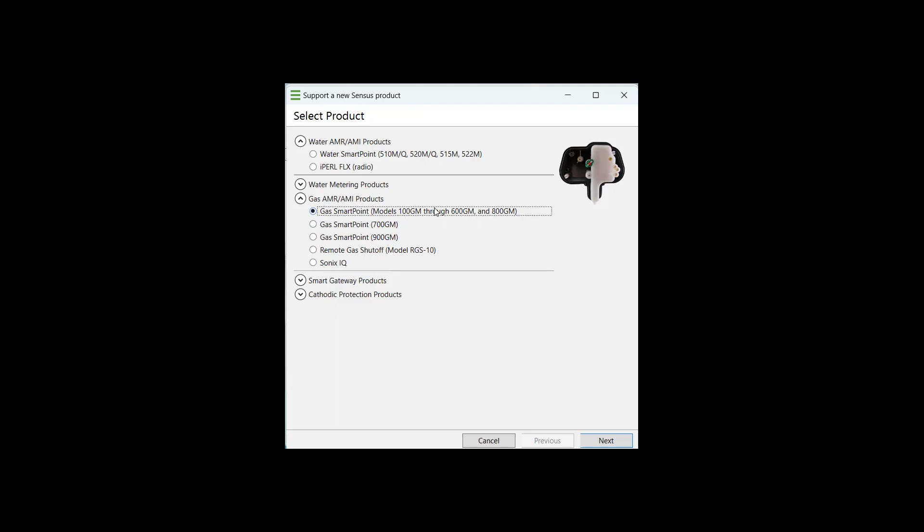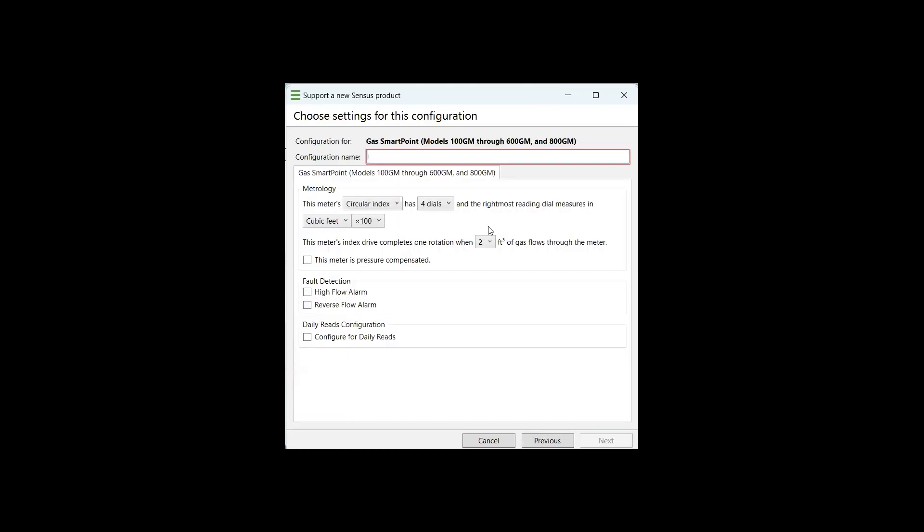That's going to be your 100 GM for your R275s, 300 GMs for the AC250s or other side mount American diaphragm meters, the 500 GM, which sits atop a Sensus diaphragm, a top mount Sensus diaphragm meter, the 600 GM, which is for an American top mount style diaphragm meter, and we don't see the 800 GM very often anymore. I believe that's a Schlumberger model there. So we're going to go ahead and stick to the 100 GM through 600 GM and 800 GM and select next.